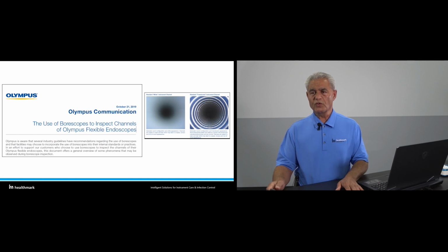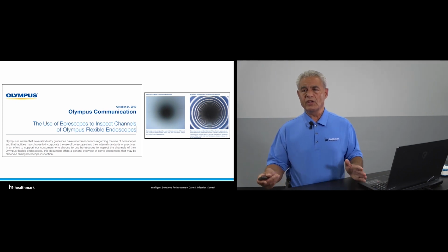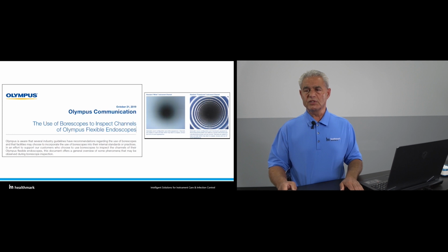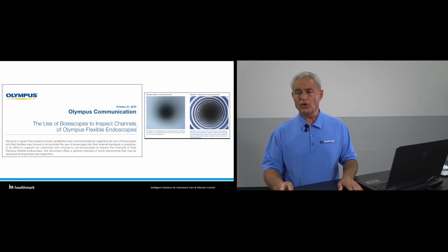People have been using borescopes for more than 10, 15 years. I started using a borescope in 2009, but as you see, Olympus in October 2019 released this communication, and they said that they are aware that most of their customers are using borescopes for inspecting inside the lumen, and they basically sent some photos of what a clean endoscope looks like and what a scope with some debris inside looks like.